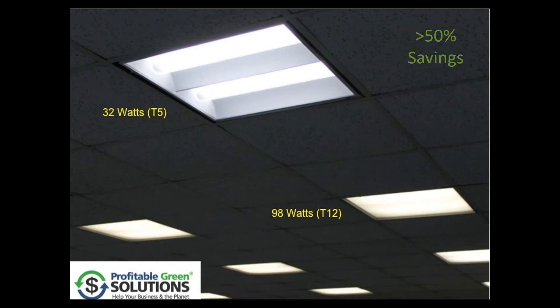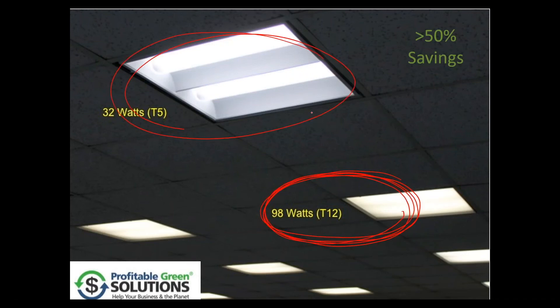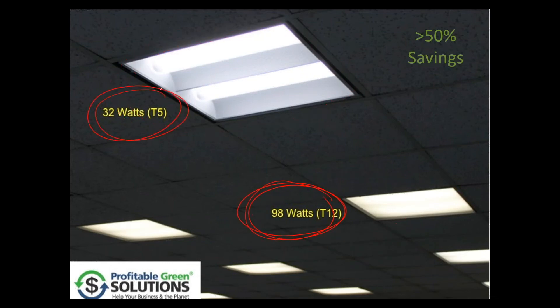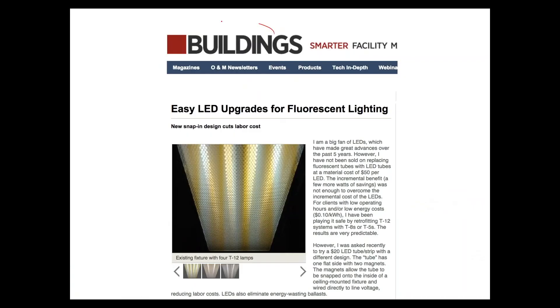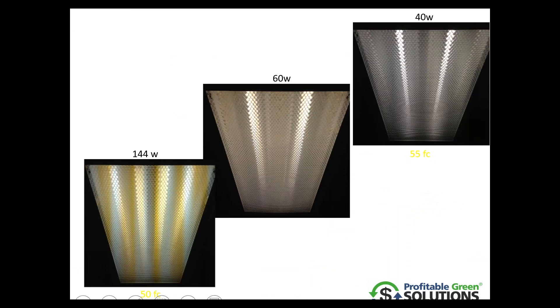Here's an example of a retrofit where the existing fixture was a T12 — really old — but it could have been a T8. It was upgraded to a T5 fixture; today it could be done to a shielded LED. You can see the difference: 98 watts down to 32 watts, pretty substantial. Lighting is changing all the time. Forty years ago we had lighting that would take 144 watts to accomplish something, and you can see the progression of newer technologies getting more light, cleaner light, brighter light, better CRI — with less watts.